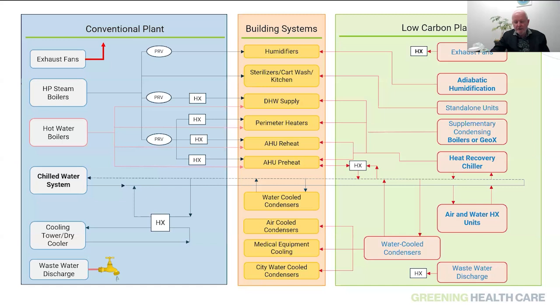In our view, perhaps the biggest single opportunity, and one where I would predict that within 20 years every hospital on this call will have at least one heat recovery chiller serving them, and we'll hear today how that works. Then the loads that feed into that chilled water system at the bottom of this chart: water-cooled condensers, air-cooled condensers, so many places within hospitals where we reject heat right through the heating season, over time being able to pull that back and recover it. So we're in transition from the left side to the right side. It involves everybody, and it starts now. Next slide, please.